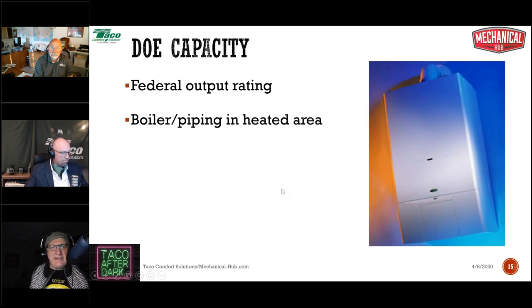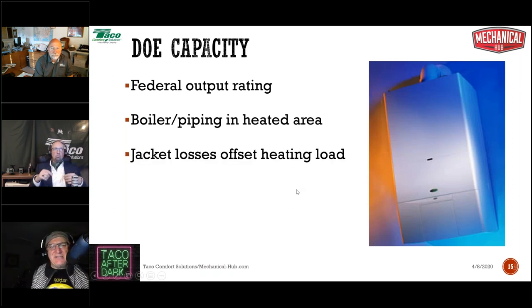What the DOE presumes, all right, is that the boiler and all of the associated piping is installed in a heated area. So in that case, any jacket losses or piping losses are considered useful or usable heat, all right? And they will help offset the calculated heating load.